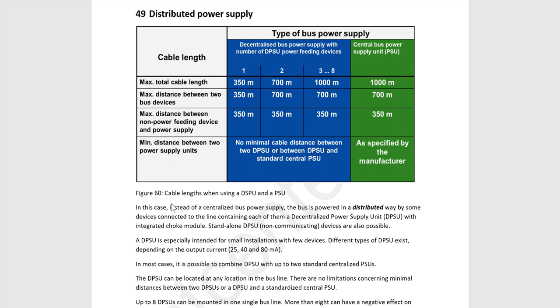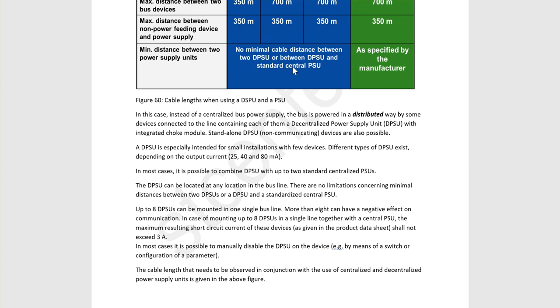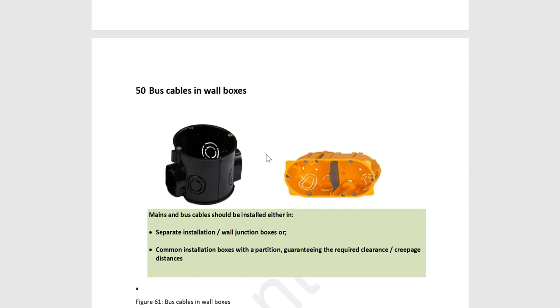For example, if you use the Synco 700 from Siemens that is used to control the boiler and chiller and air handling unit based on KNX, okay, it has the connection to the 230 volt AC directly, and it has its own power supply unit. So in that case, you should always follow this table to see how many devices you can power it up with the decentralized or distributed power supply units, because the power supply units that I mentioned before and we use for most of our project is centralized power supply unit. We put some power supply in center in electrical cabinet and power up whole of the line. Okay, but in the decentralized power supply unit, it's a bit different. The current is 25, 40 and 80 milliamp in this case, and you cannot connect so much devices. You can read it by yourself here.